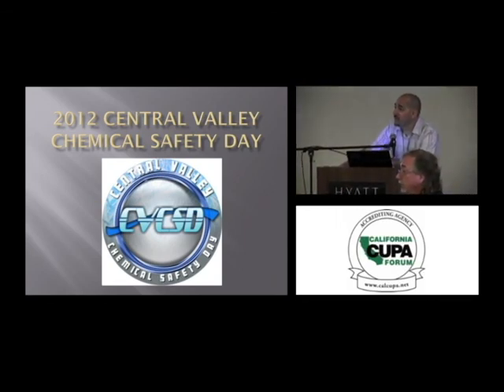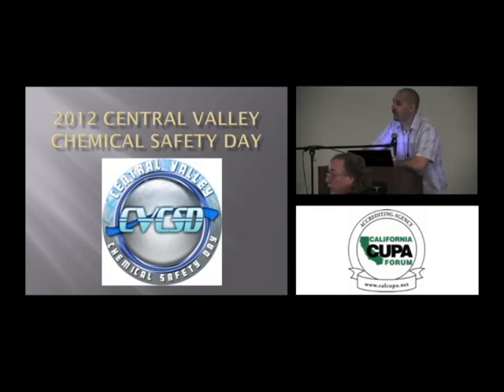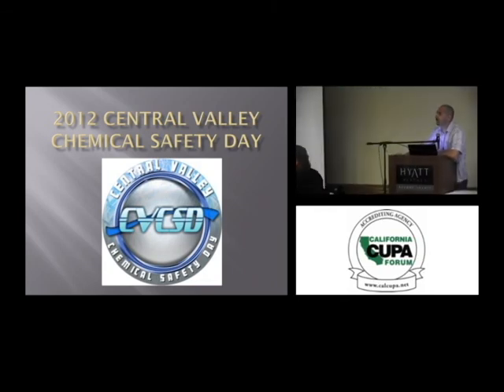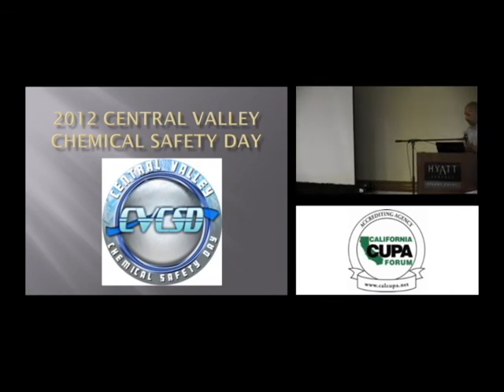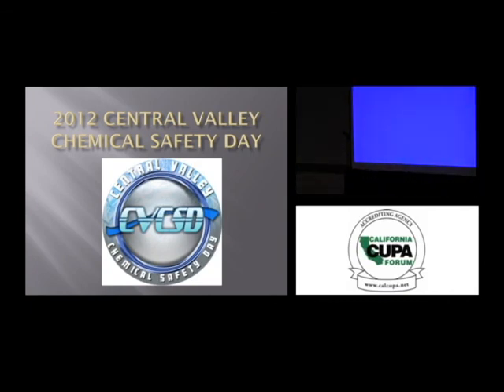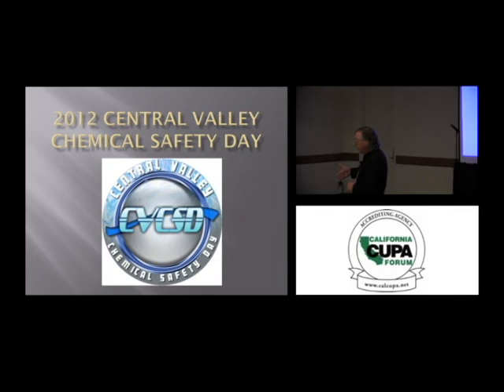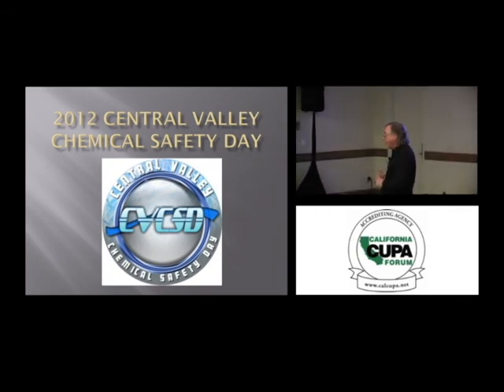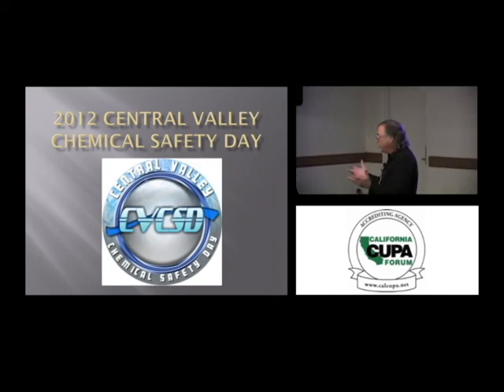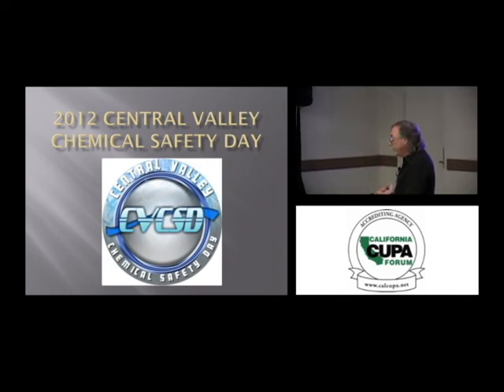What type of filter would you recommend putting on those machines you talked about, the dust? There's different ones. We'll do it 2 ways. If we're bringing in outside air, we'll put filtration on the walls, on the intakes, and you can get a washable mat from Grainger's. It's blue. It's a fiberglass-like netting, and they can just take it off. It's reusable. Let's be green. It's recyclable. Wash it, put it back on.